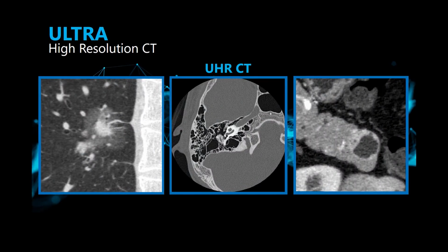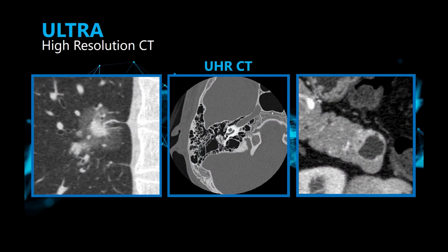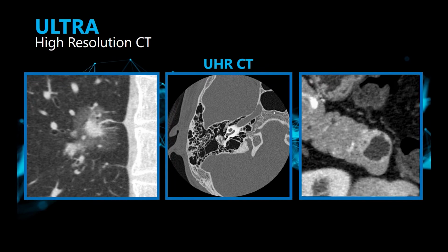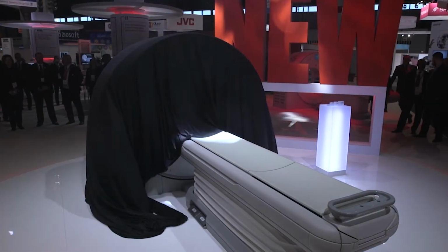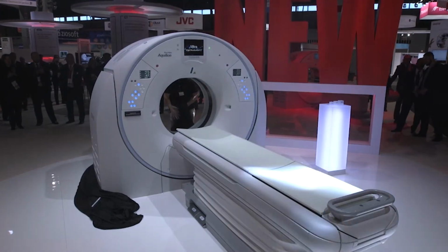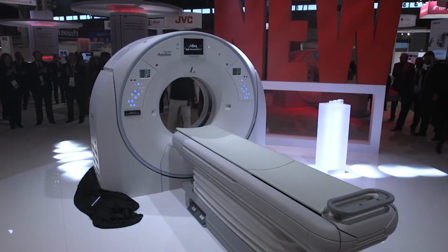The Aquilion Precision introduces a brand new ultra-high resolution CT detector, with detector elements now the size of 0.25 of a millimetre. This is by far the smallest in the industry. These new 0.25mm detector elements enable us to resolve structures down to 150 microns, which is about the size of half a grain of salt.